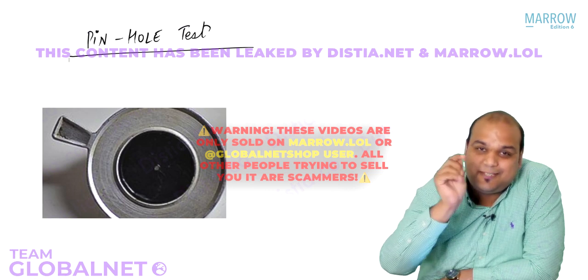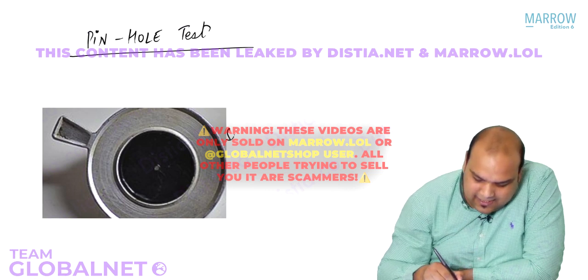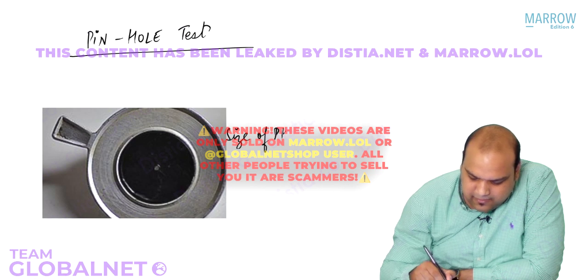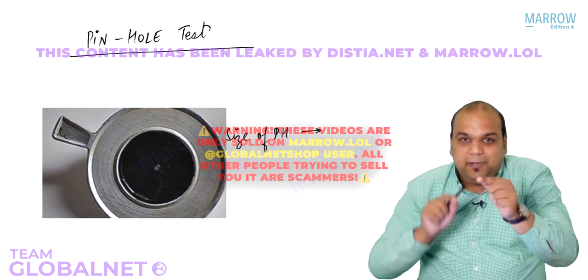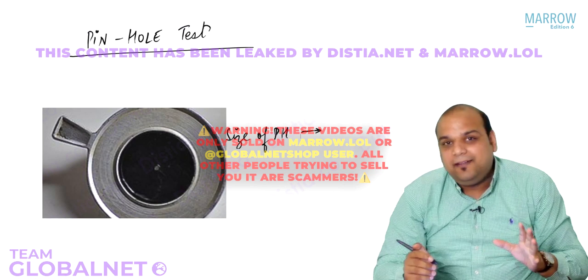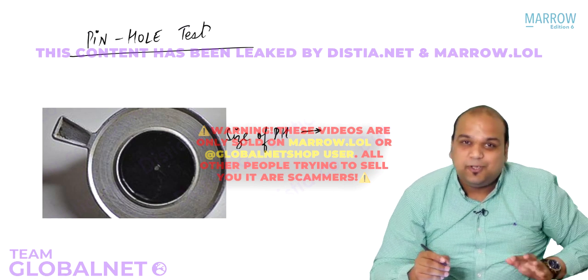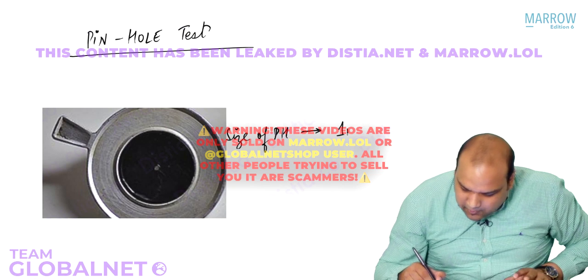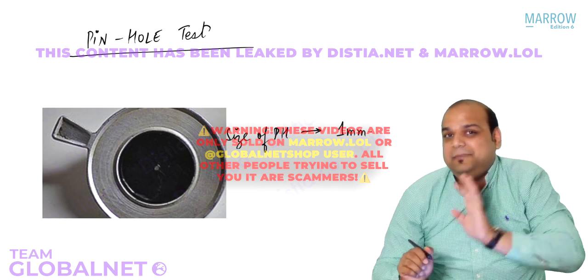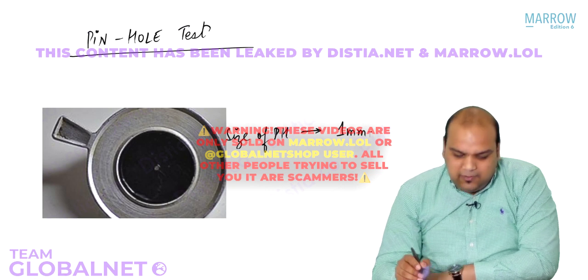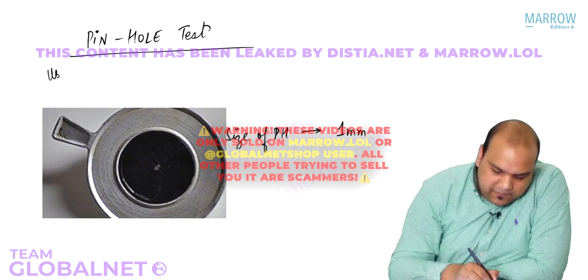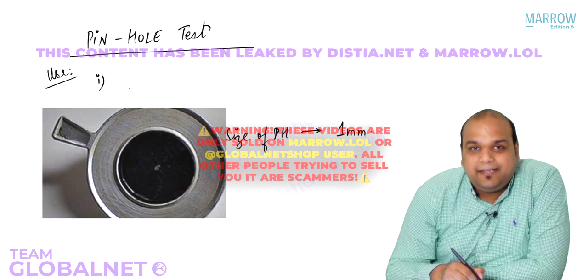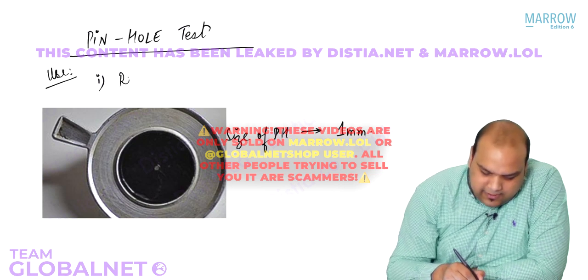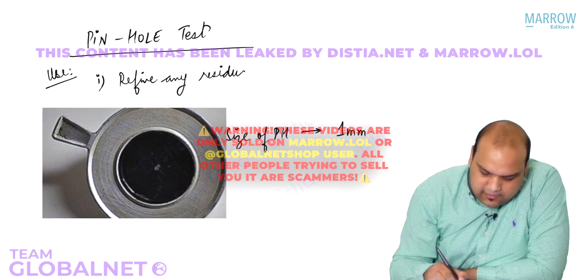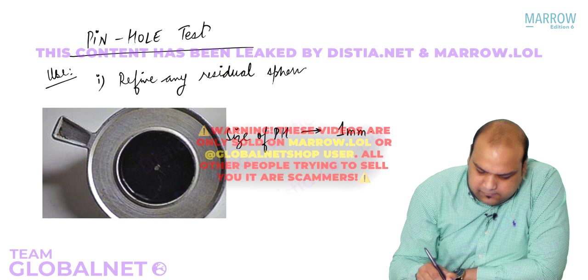In the center of the disc, there is a small hole. What is the size of the pinhole? If you are used to creating a pinhole in a piece of paper with your pen, you are creating it wrongly. Your size is not constant. Yes, the size of the pinhole has to be 1 mm, 1 millimeter. Please remember this. Now, what is the use of the pinhole, everybody? The use of the pinhole is that it can find out, it can refine any residual spherical error.